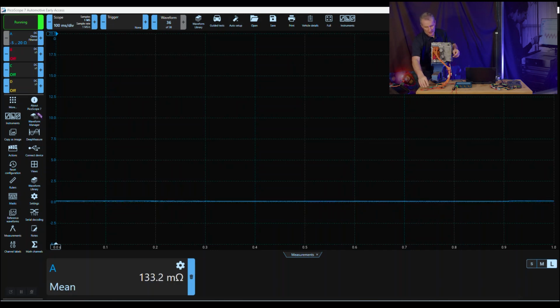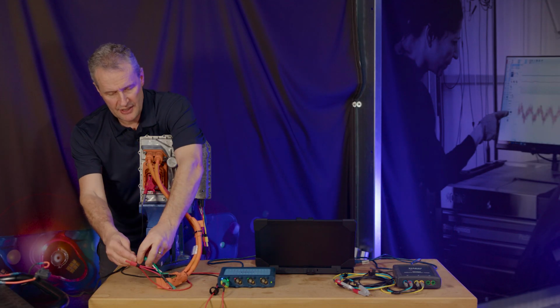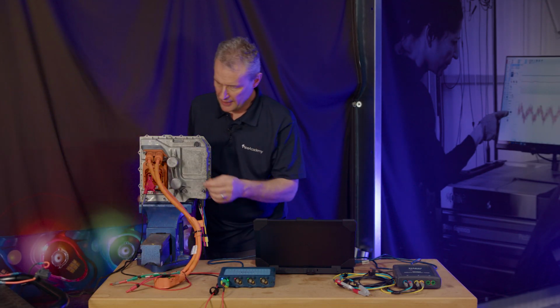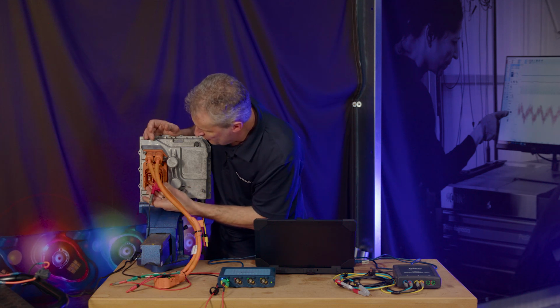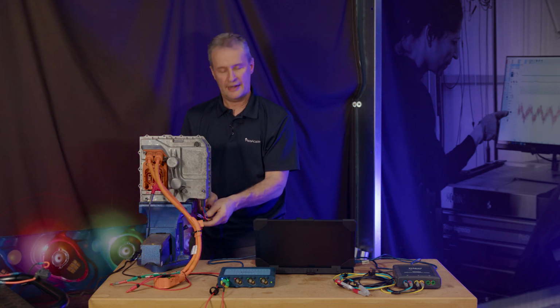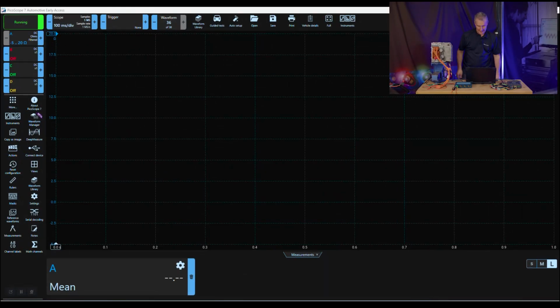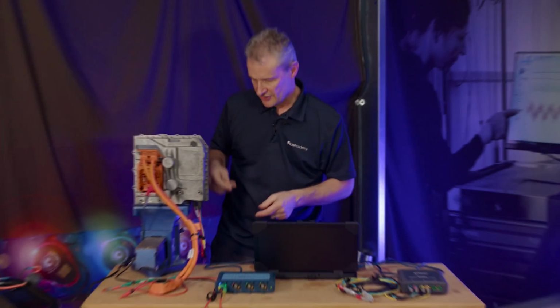Let's repeat the process. We'll now move across to the negative contactor, moving across to the other cable, the other input, and now energizing the negative contactor. PicoScope is still indicating an open circuit. Let's just see if there is anything across there. We're changing the range now, up to 2 kilo ohm, 20 kilo ohm, 200 kilo ohm, 2 mega ohm. It's just open circuit. So there we have it, open circuit negative contactor. Not on the coil side because we can hear it energizing, but on the contact side.